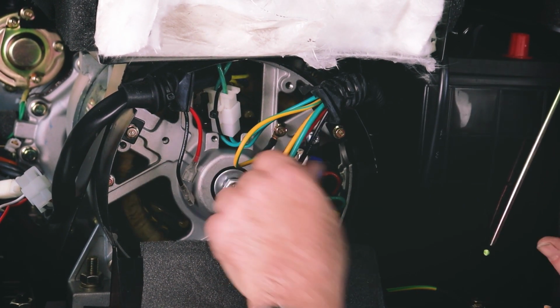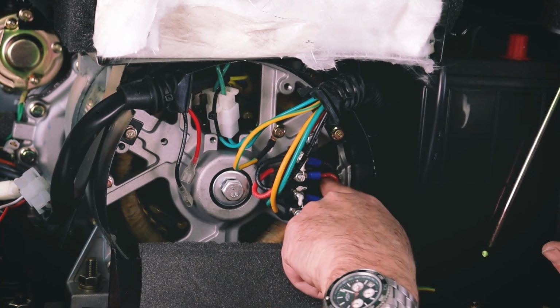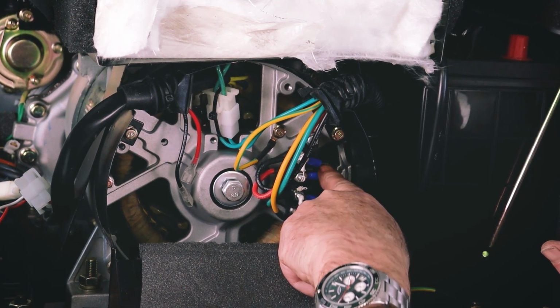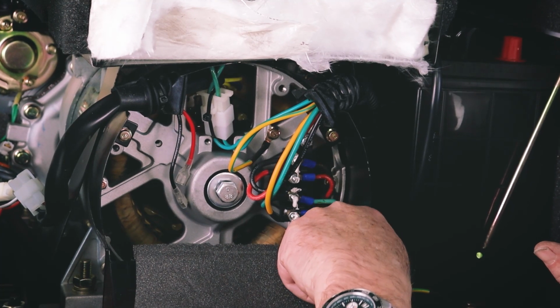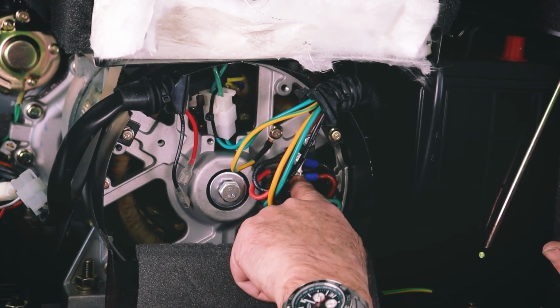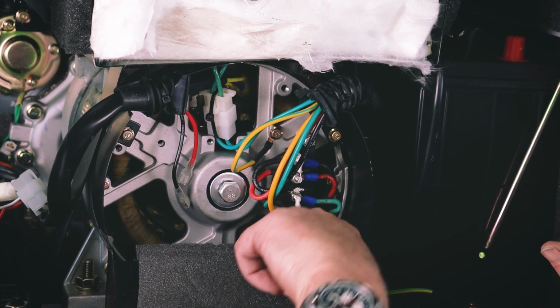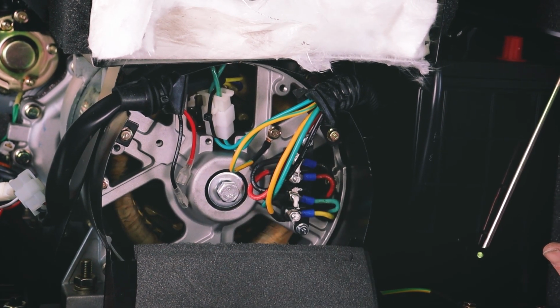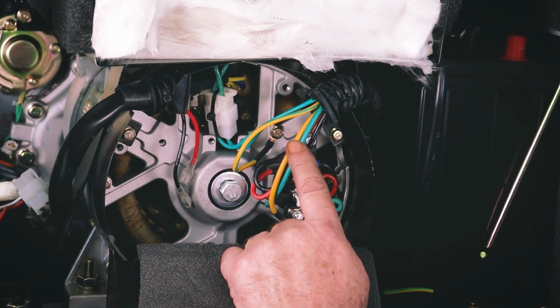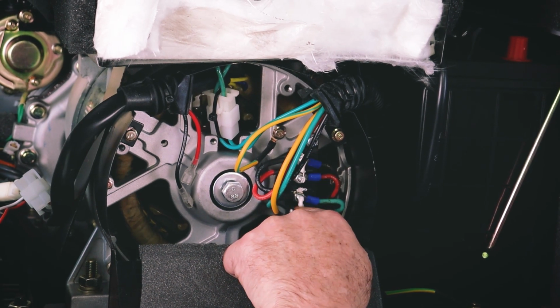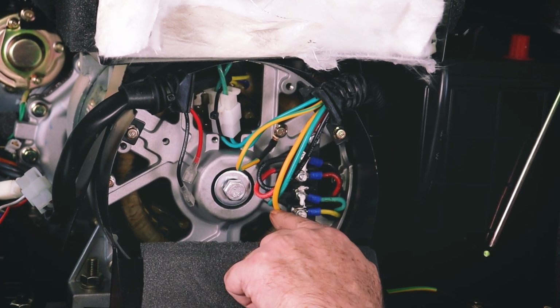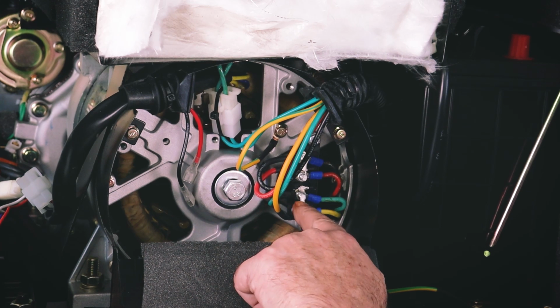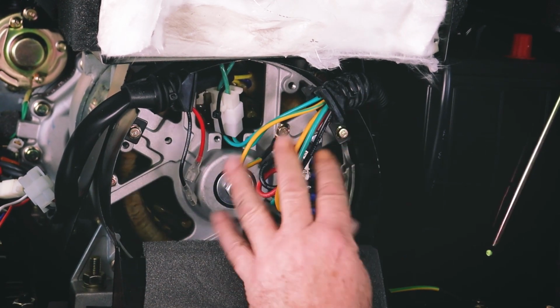These 4 wires on this side are the 4 wires coming out of the windings of the alternator, and they're simply connected on these 4 poles: yellow to yellow, green to green, red to red, and black to black. If your color coordination isn't like that, take a photo to show where these wires were when you took them off - if the machine was working, it will have been correct.